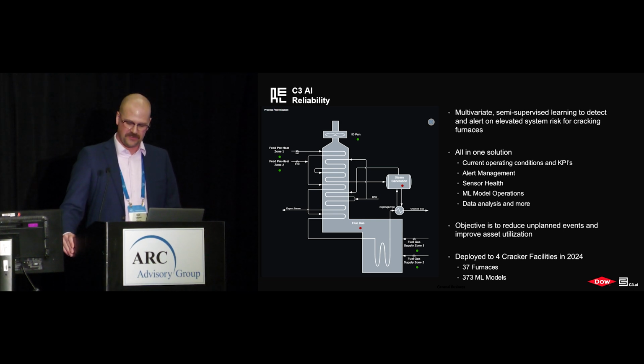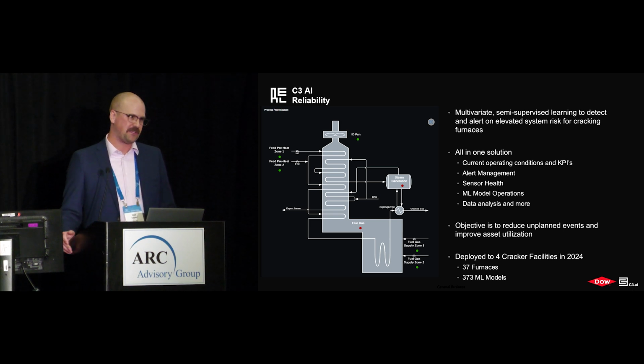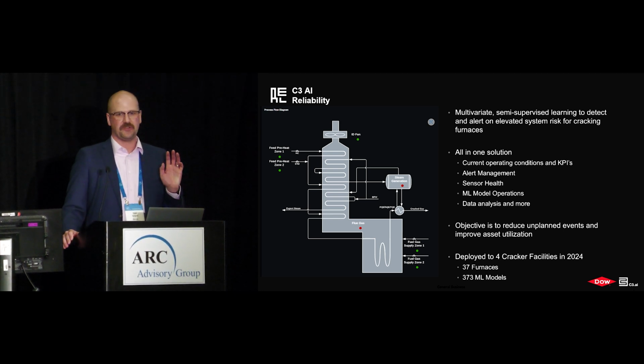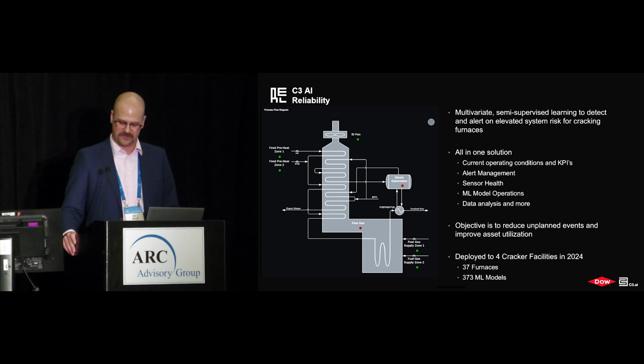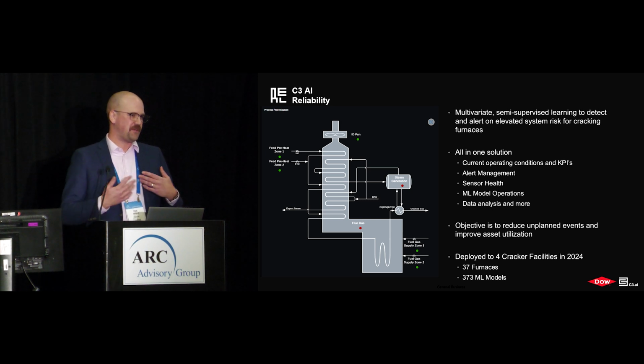So this is an all-in-one solution that allows us to monitor our current operating conditions and some key performance indicators for our facilities. It has a full alert management suite that allows us to monitor alerts from when they're triggered, track investigation, resolution, and keep a long-term history of the closure of those alerts. It also has a sensor health module that monitors all of the sensors and the data coming into the application to ensure that we're getting good data: it hasn't failed high, failed low, we're not missing data, or it's not stagnant for a period of time.